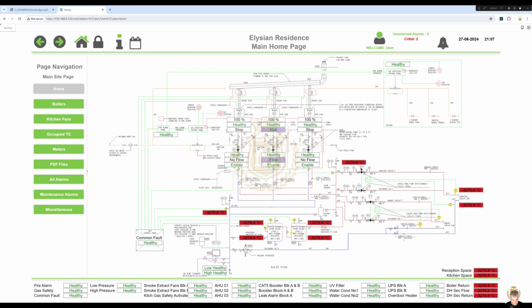These are my secondary pumps, 4 and 5, going to the header, coming from the header into there. So that is definitely my landlord circuit, flow and return, and we definitely got that right. But now we've got amenity circuit. That's got to be on the other controller. So what we do, once we've done the other controls, we've got to bring those points via network back into this controller to display at least those 2 points there, and maybe to display other stuff that's on there.